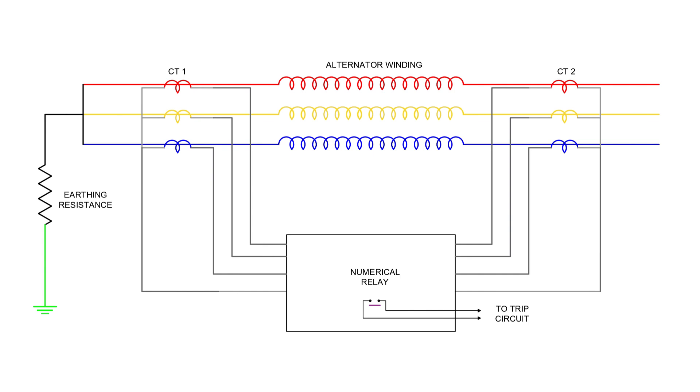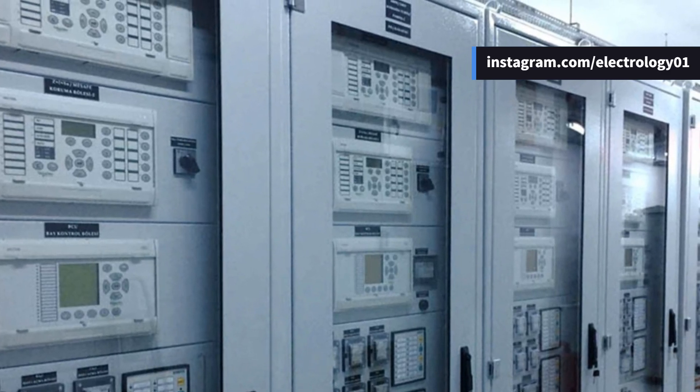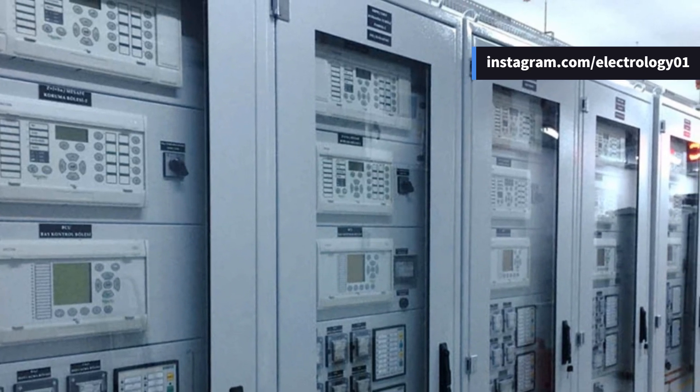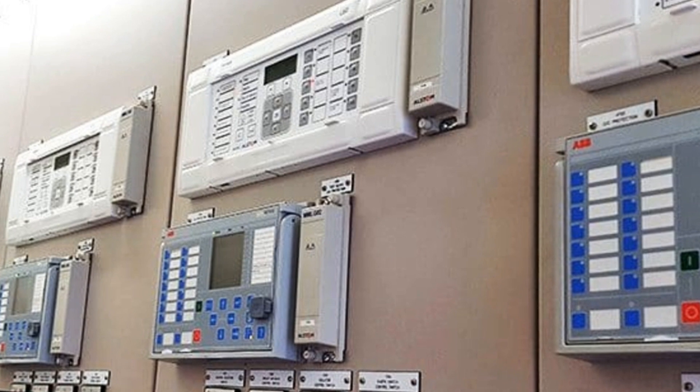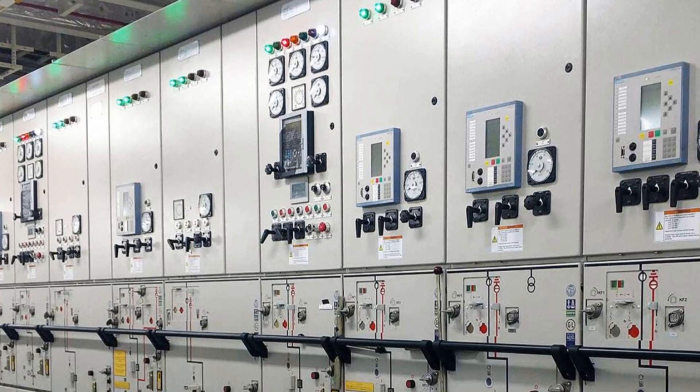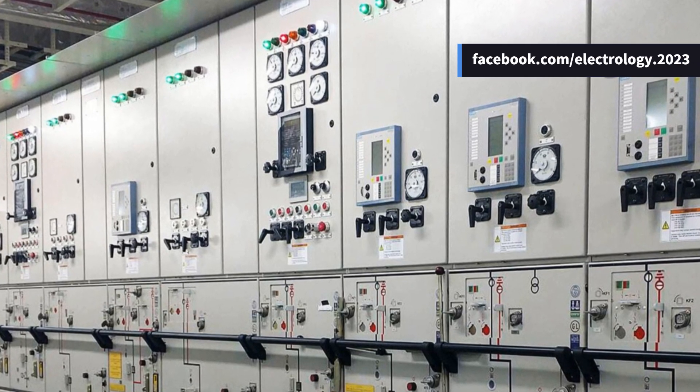If it detects a difference, meaning a differential current above the relay's set threshold, it instantly sends a trip signal to isolate the alternator by opening the circuit breaker. Numerical relays offer improved accuracy, faster operation, self-diagnostics, and communication capabilities compared to older electromagnetic relays, making them the preferred choice in most high-voltage installations today.